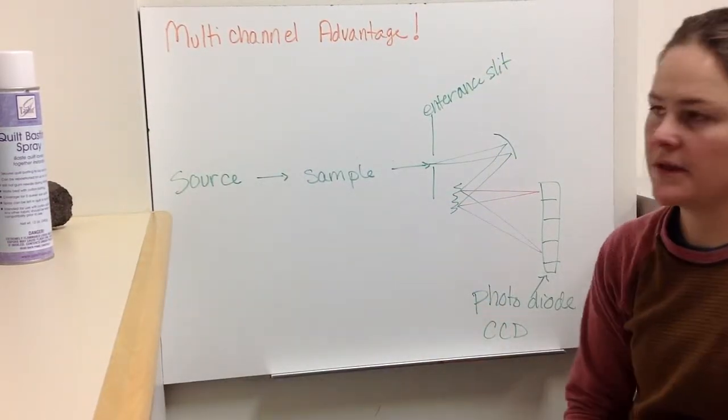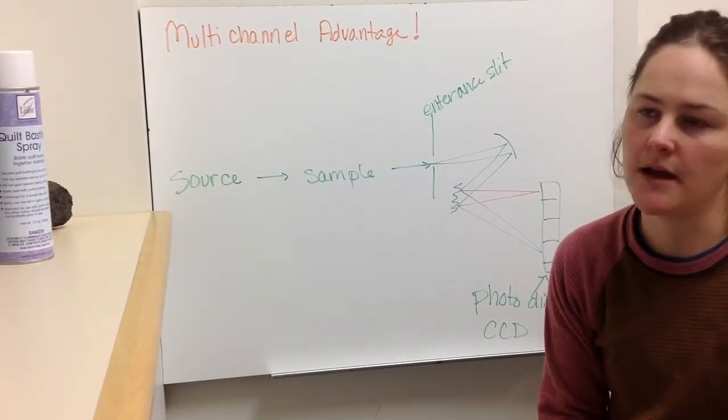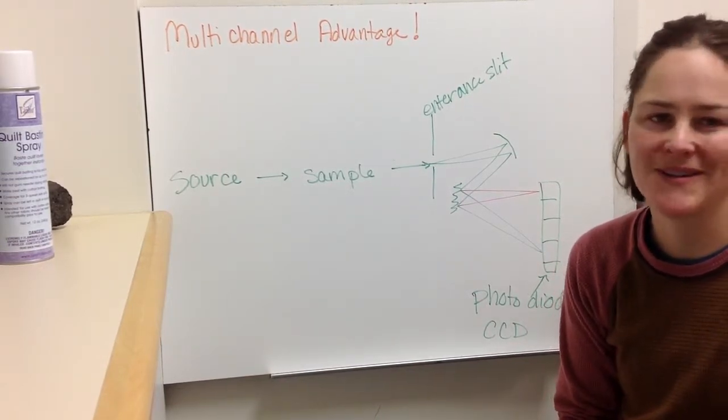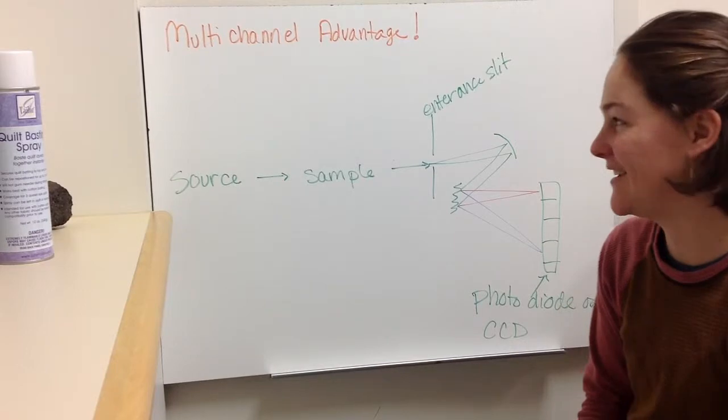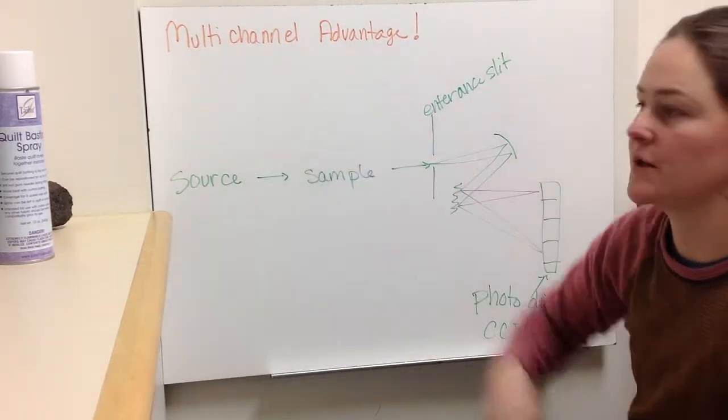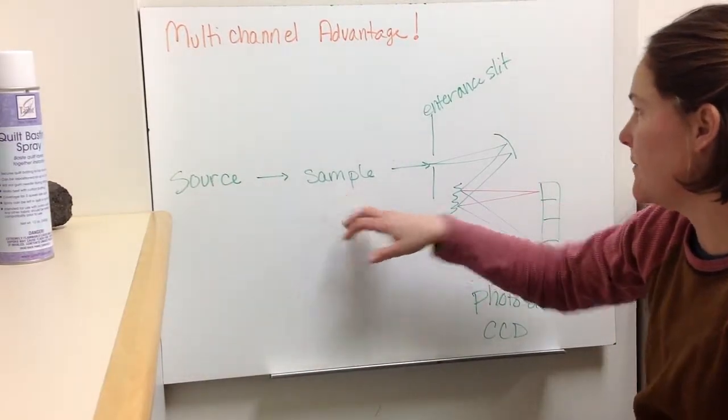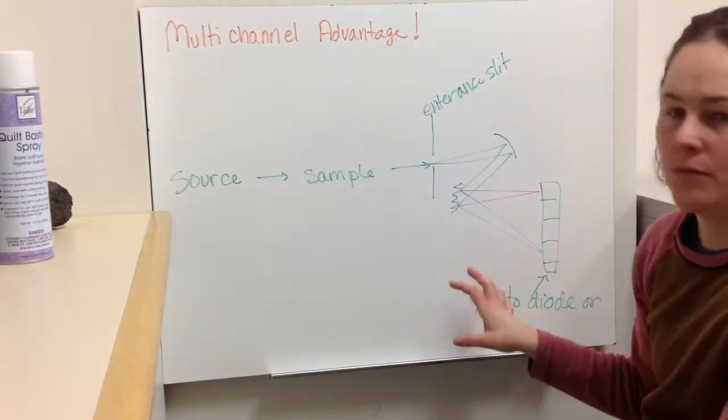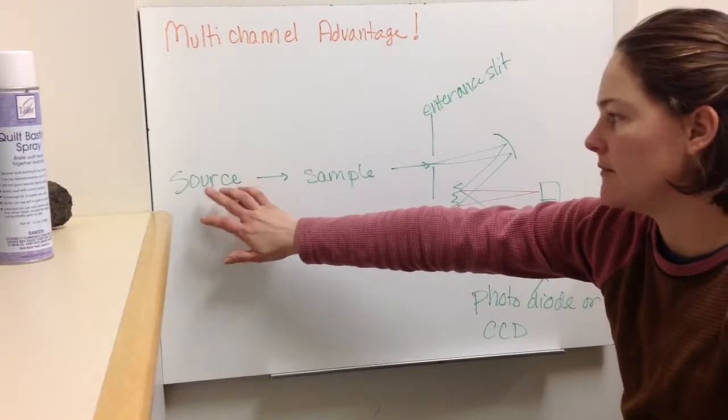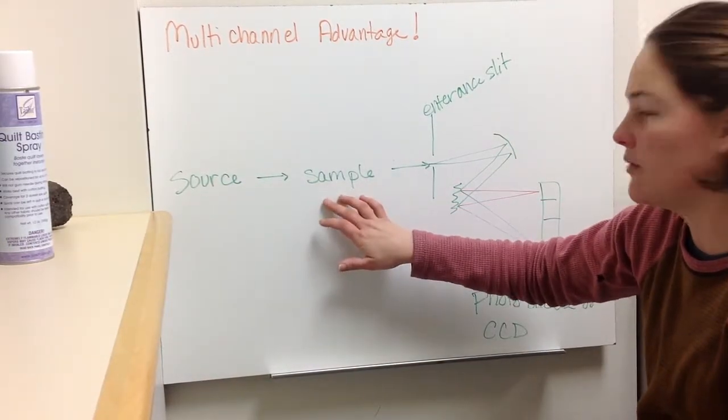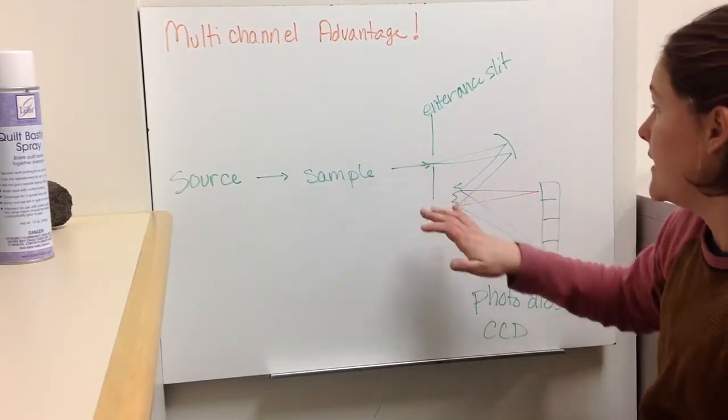But these double beam instruments, I'm sure that there's still a lot in use, but we actually have some really way better technology now. We can actually detect a bunch of different wavelengths all at the same time. So in this case, you would have the source, the sample, and then instead of having a full-blown monochromator, you're having many wavelengths coming from your source, interacting with your sample all at the same time.